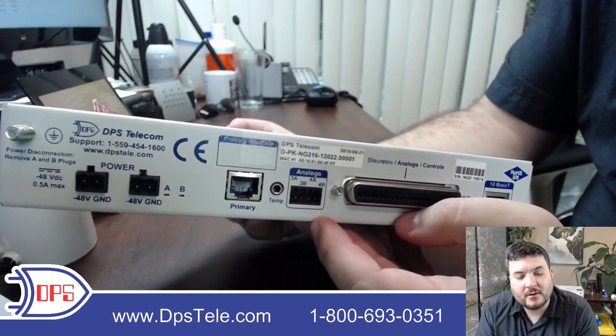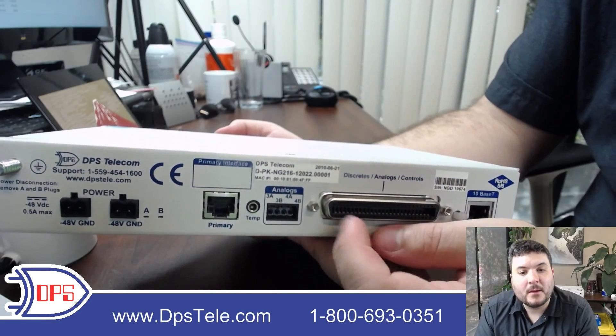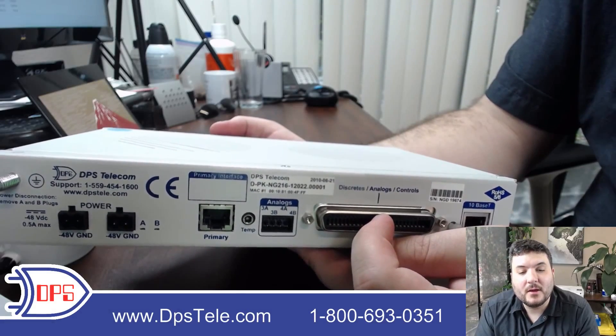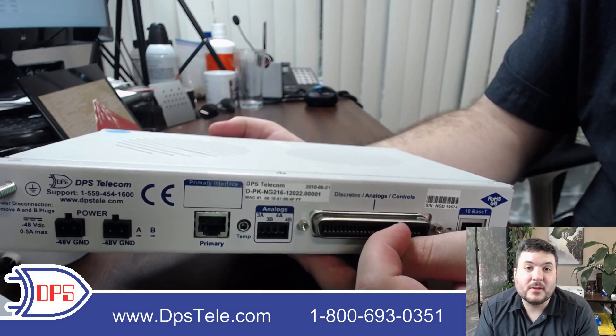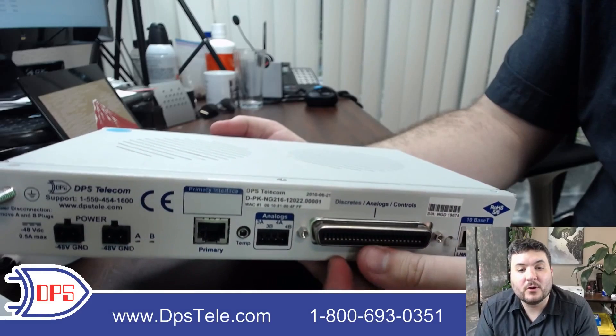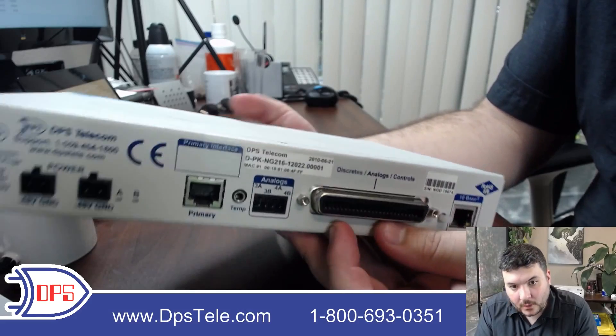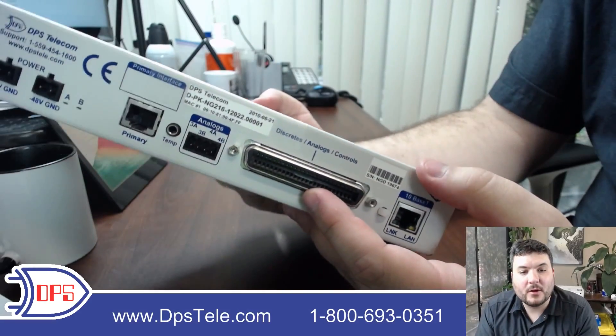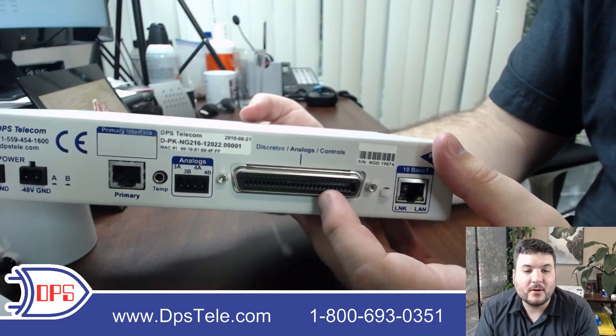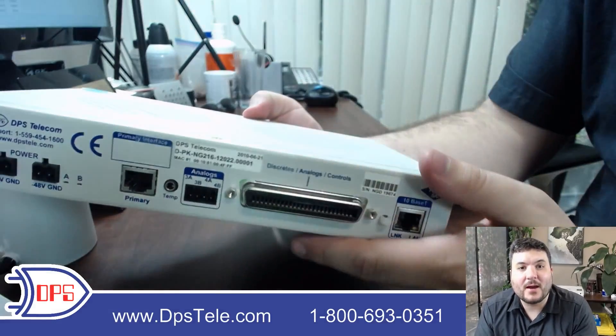Then we have our analog inputs — these are analogs three and four, because this 50-pin connector didn't have enough capacity to hold everything. This connector will have 16 discretes — that's the '16' in the 216 name — two control relays, with build options available for even more if you need additional control relay outputs, and the first two analog inputs. The last two analog inputs are on this separate connector. The Amphenol 50-pin connector is common if you want to go to a 66 block or a wire wrap panel, which is a very common industry terminator, and we have a variety of wiring options available.